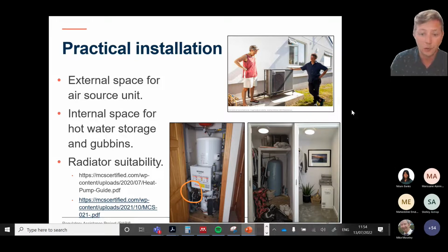You also need internal space for hot water storage and general gubbins. Gas combi boilers, which are popular, don't have a hot water tank. For heat pumps, you need some sort of hot water storage because the energy output isn't generally high enough for instantaneous hot water. There are ways around that, like electric showers or taps, but you get much better efficiencies using the heat pump for hot water, so you need somewhere to put it. A traditional installation has a hot water cylinder - looks like a 200-litre one to me - along with the controller and general gubbins: circulation pumps, a filter, heat exchanger, and an expansion vessel. You can fit all of that into a cupboard about one metre squared, as I've done in my own house. It can be a bit tight, but doable, and I think as innovation happens in the market it will get easier.